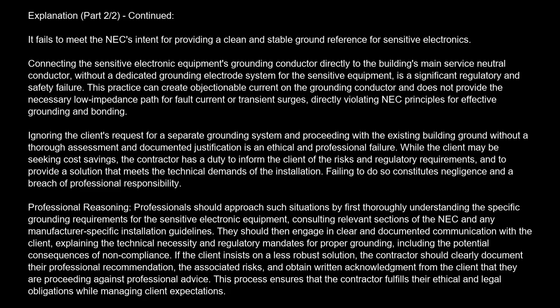This practice can create objectionable current on the grounding conductor and does not provide the necessary low impedance path for fault current or transient surges, directly violating NEC principles for effective grounding and bonding. Ignoring the client's request for a separate grounding system and proceeding with the existing building ground without a thorough assessment and documented justification is an ethical and professional failure. While the client may be seeking cost savings, the contractor has a duty to inform the client of the risks and regulatory requirements, and to provide a solution that meets the technical demands of the installation. Failing to do so constitutes negligence and a breach of professional responsibility.